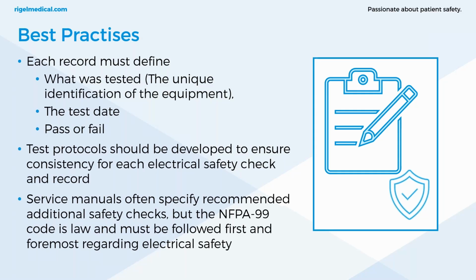Test protocols should be developed to ensure consistency for each electrical safety check and record. The aim of electrical safety in NFPA 99, and that in all electrical safety standards, is just to limit the leakage currents that can cause any injury to a patient or user. So it's always best practice just to test where a risk to electrocution may occur regardless of what the minimum requirements of the standard or code are.